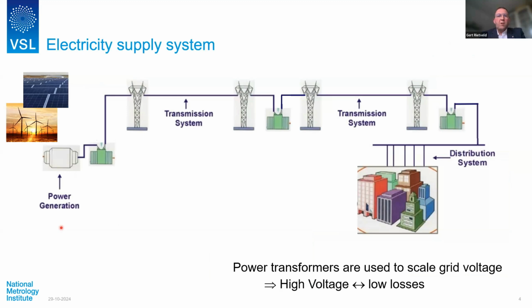So this is, I would say, a sketch of our electricity supply system. It starts with power generation, conventional generation, but nowadays also wind and solar generation. And then there's a power transformer to scale up the voltage to the level of our high voltage transmission system. And the high voltage really helps to reduce current and thus to reduce losses. And that's why we have the high voltage. But then, of course, at the place of use in our distribution system, we need to scale it down again to the level that we can use it. So power transformers are really key components in the grid.